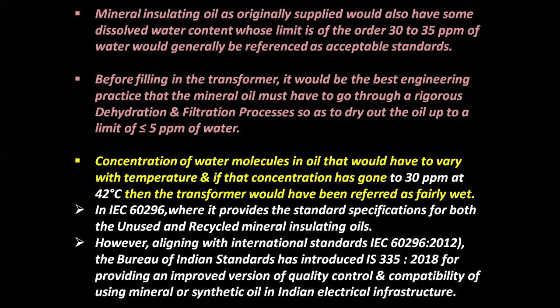Before filling in the transformer, it would be the best engineering practice that the mineral oil must go through rigorous dehydration and filtration processes so as to dry out the oil to a limit of less than or equal to 5 ppm of water.